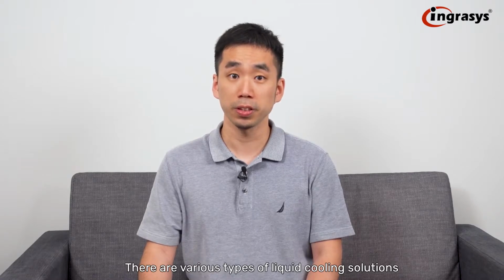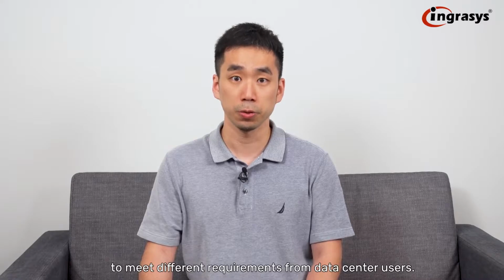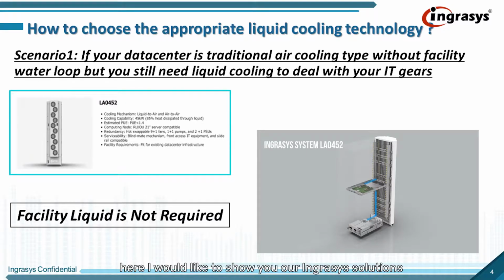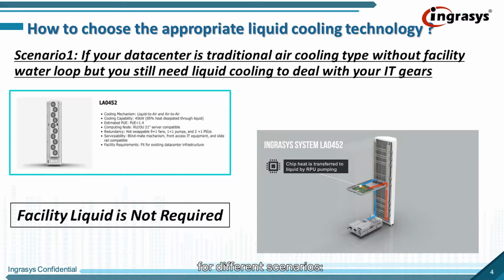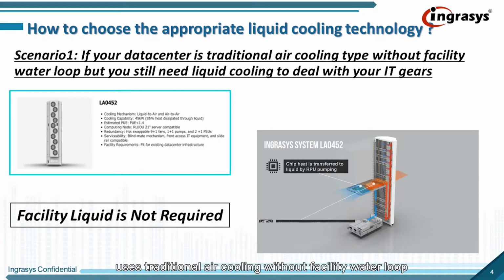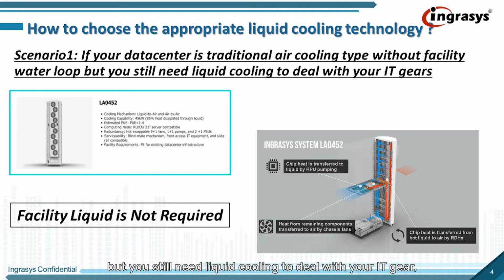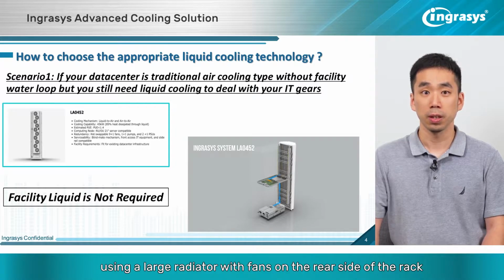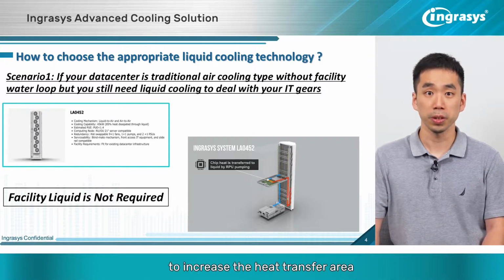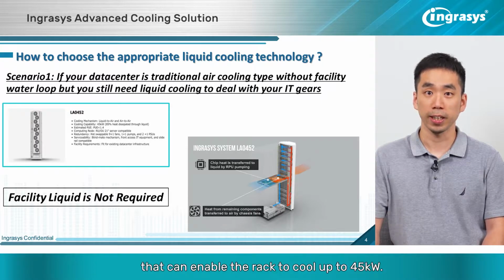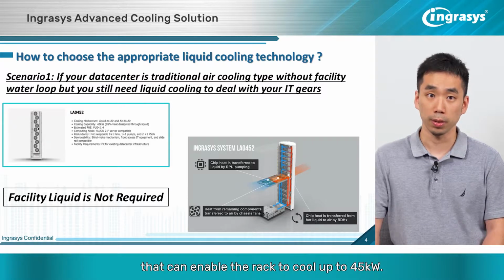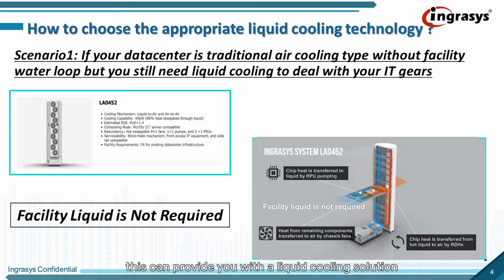There are various types of liquid cooling solutions to meet different requirements from data center users. Thus, here I would like to show you our Ingrasys solutions for different scenarios. If your data center uses traditional air cooling without a facility water loop, but you still need liquid cooling to deal with your IT gear, our liquid-to-air rack, LA0452, is the one that can fit your requirements. The key idea is using a large radiator with fans on the rear side of the rack to increase the heat transfer area and the airflow rates that can enable the rack to cool up to 45 kW.